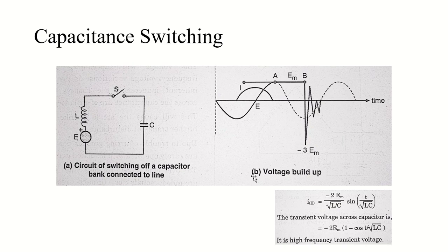Now let's discuss about capacitance switching. In power systems, a hazardous condition occurs when a capacitor bank connected to a long transmission line gets disconnected. Consider the power system shown in this figure — a simple basic circuit having voltage source E, L as the source inductance, and C as the capacitor bank connected to the system through switch S. Now let's consider that switch S interrupts the capacitor current at some instant A, and at this instant the capacitor is charged to its maximum value EM.